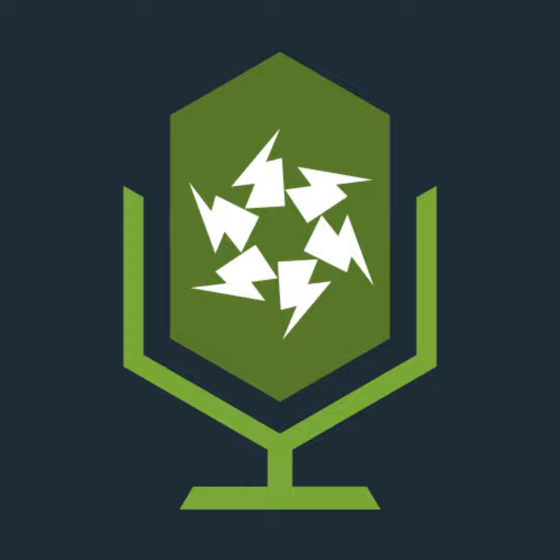If I take a B-type circuit breaker and I replace it with a C-type circuit breaker, whilst I've added no resistance and I've changed no load, I have changed the performance characteristics of the protective measure of automatic disconnection of supply. Because when I change a B to a C, I require twice the fault current, which means I now need half the earth fault loop impedance.